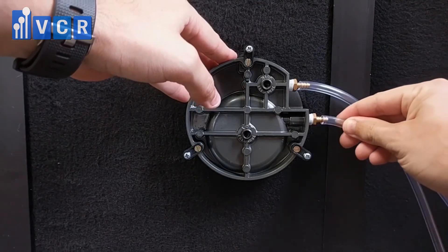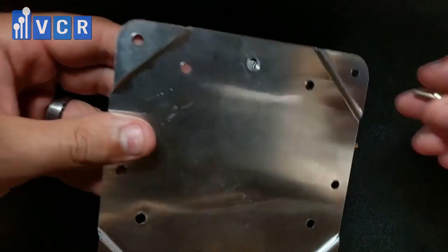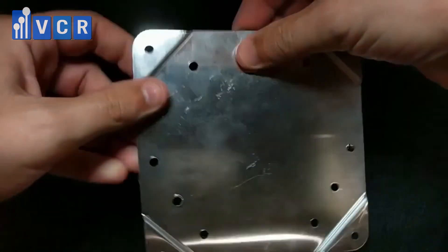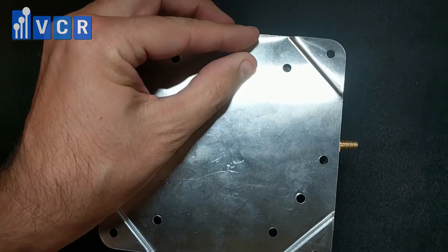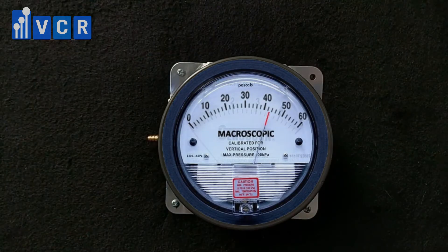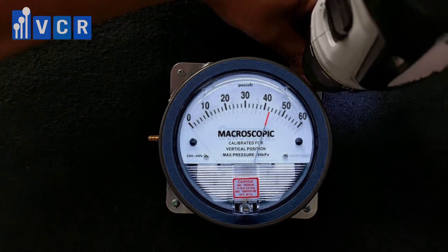A second common option for installation is surface mounting by using a surface mounting plate. For this application, the brass fittings will need to be installed in the ports on the side of the gauge and the plugs will need to be installed on the back. Once the fittings and plugs are installed, use the small screws provided to attach the mounting plate to the back of the gauge. With the gauge secured to the plate, use the additional screws to mount the bracket to the preferred surface.